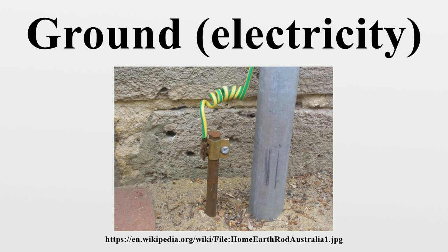For particularly demanding applications, the main technical ground may consist of a heavy copper pipe, if necessary fitted by drilling through several concrete floors, such that all technical grounds may be connected by the shortest possible path to a grounding rod in the basement. Lightning protection systems.